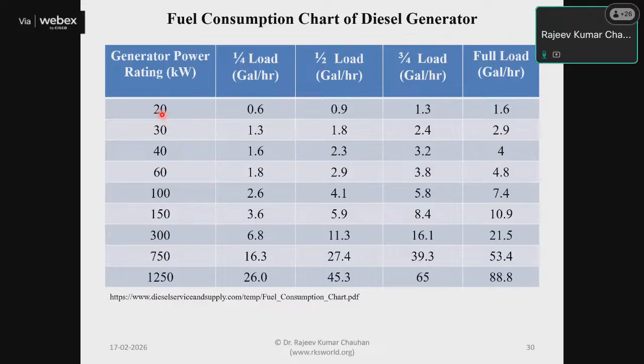For example, if we run a 20 kilowatt generator at quarter load, it consumes 0.6 gallon per hour. At half load, 10 kilowatt output, consumption is 0.9 gallon per hour. At 75% load capacity, consumption is 1.3 gallon per hour. And at full load, consumption is 1.6 gallon per hour.